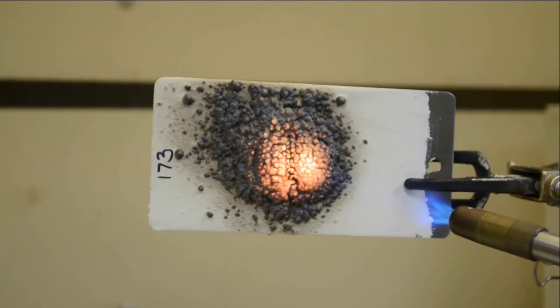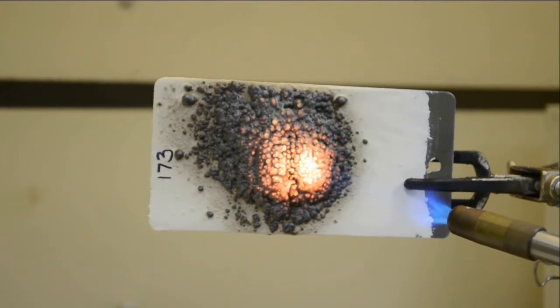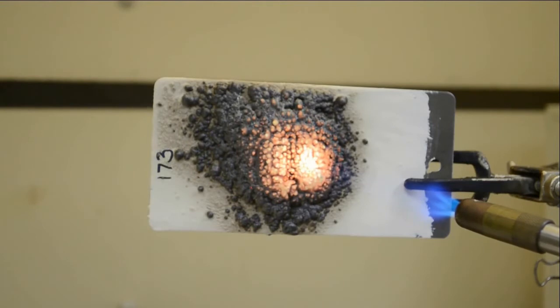Flame Control 173 has been subjected to rapid rise fire conditions and maintains the permissible temperature performance criteria as specified in the UL 1709 and ASTM E119 tests for a period up to 2 hours.